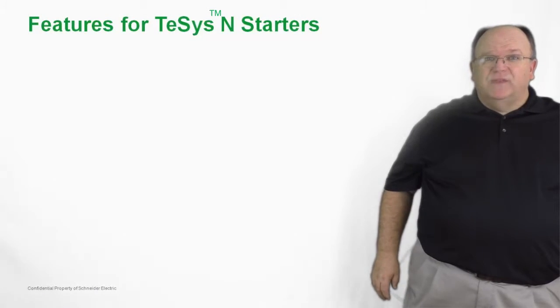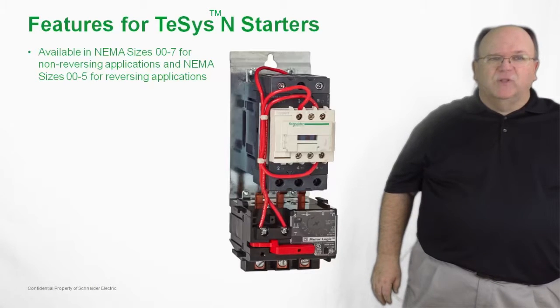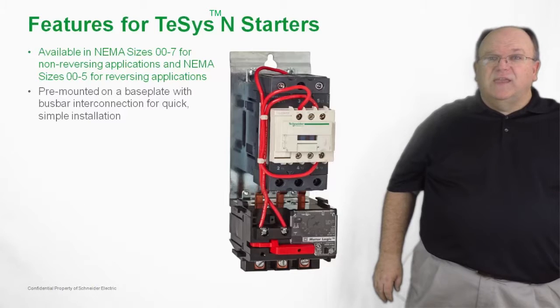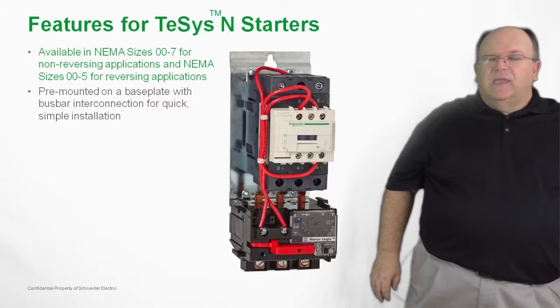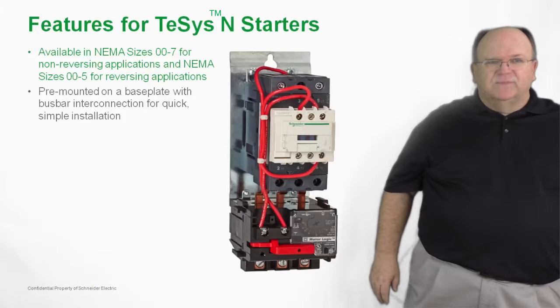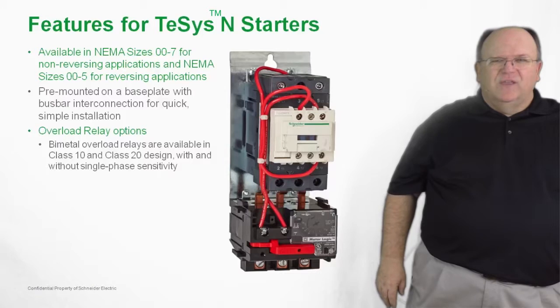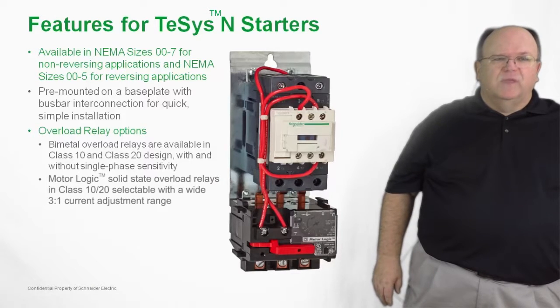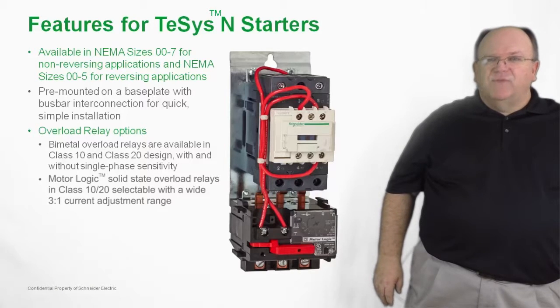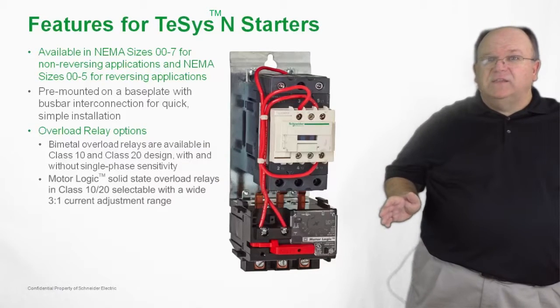The TeSys N family of NEMA rated motor starters are available in NEMA sizes double-aught through 7 for non-reversing applications, and in NEMA sizes double-aught through 5 for reversing starter applications. All TeSys N motor starters come installed on a common mounting plate for both a contactor and overload, with quick and easy installation via keyhole slot mounting. Overload relay options include a bimetal overload with class 10 and 20 trip configurations with or without single-phase sensitivity. Motor Logic solid-state overload relays are also available in selectable class 10 or 20, with a wide thermal adjustment rating, and because they are solid state, they do not generate extra heat inside the motor control panel.